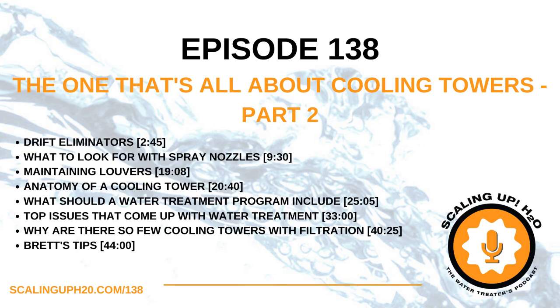There are so many people out there who will look at the bulk water temperature, the temperature in the water that's circulating, and think that's the temperature. If we're talking about an evaporative condenser, we're most concerned about those top coils where the hot ammonia is going through, and sometimes those can be in excess of 190 degrees.